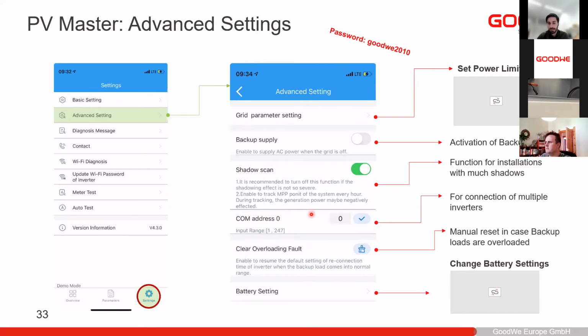In case you do not follow the recommendations of what you connect to the backup side and it's overloaded, the inverter will shut down for a few moments and then try again. After it has tried a couple of times, it will not try anymore and will be in constant failure mode, so to say. For it to reset, you need to clear the overloading fault, and that you do here. So you need to do that manually in case you do not follow the recommendation for the backup supply.